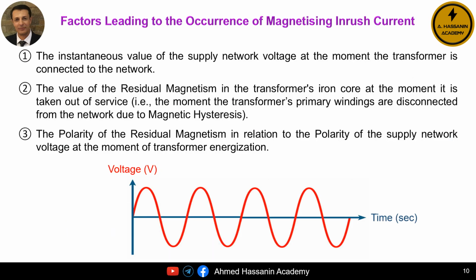Now we are saying that the phenomenon of magnetizing inrush current is a random phenomenon and does not necessarily occur every time the transformer is energized, and even if it does occur, it does not always have the same current magnitude each time. So how is that possible? We must understand that the fundamental factors behind the occurrence of magnetizing inrush current and the maximum value this current can reach depend on three main factors. The first factor is the value of the network voltage at the moment of transformer energization. In other words, as I mentioned earlier, when we energize the transformer, the voltage at that exact moment may be positive, negative, or 0. Of course, this occurs randomly and is not controlled or known in advance.